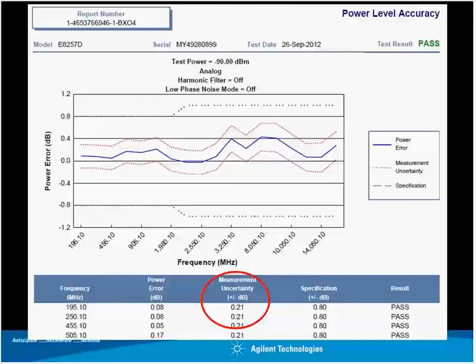And in the red circle there, you can see towards the bottom the measurement uncertainty shown in the report. So every data point is also going to include the ISO Guide GUM measurement uncertainty. And so that's also shown in this particular report. This one's also shown graphically above as well. But the important thing is that it's shown and that it's in the report.